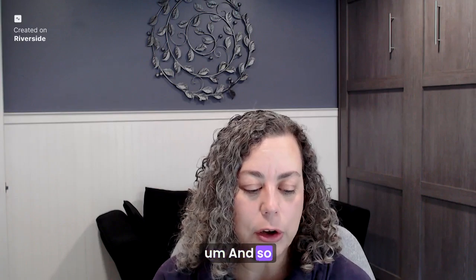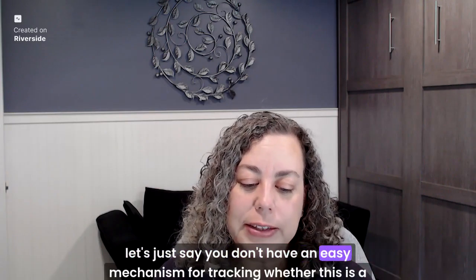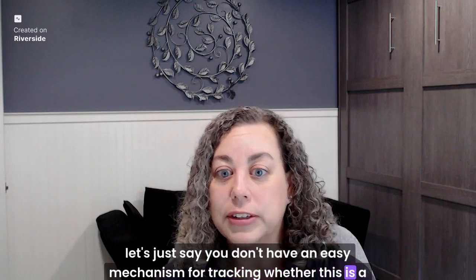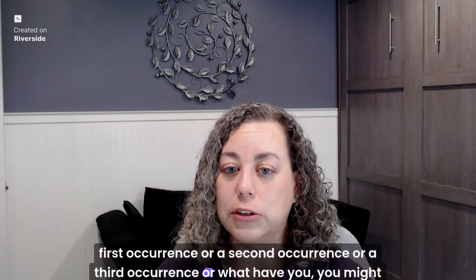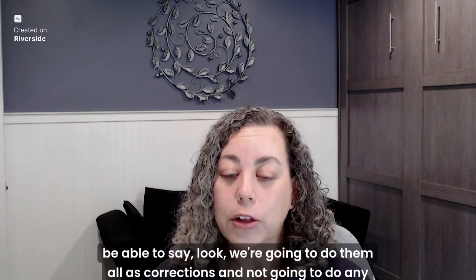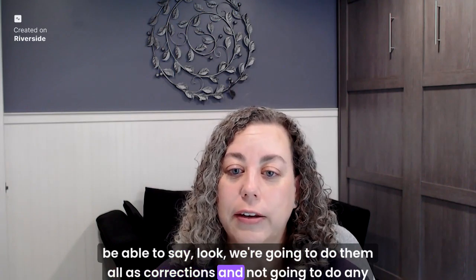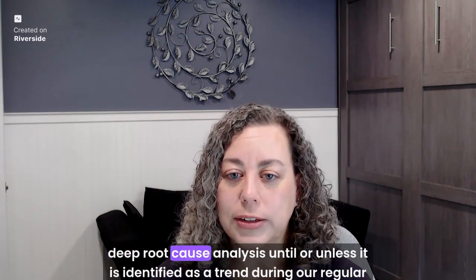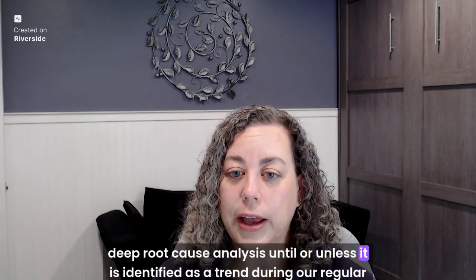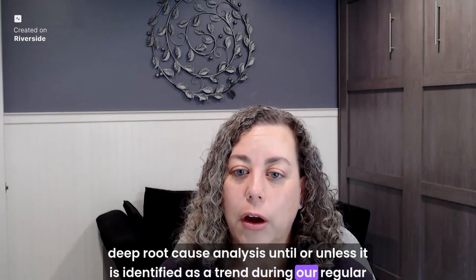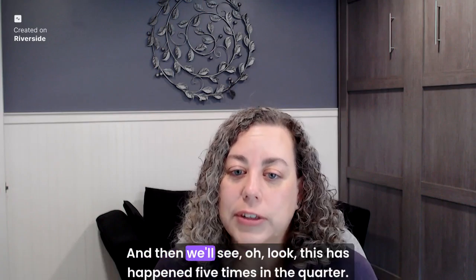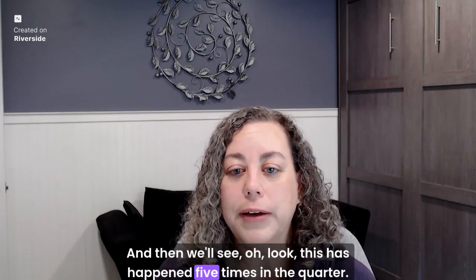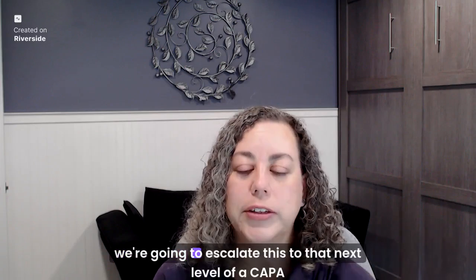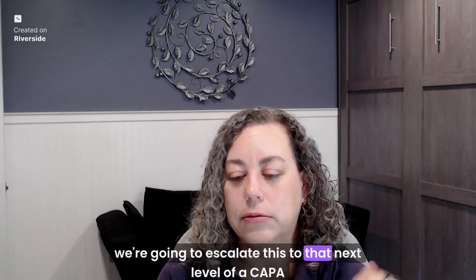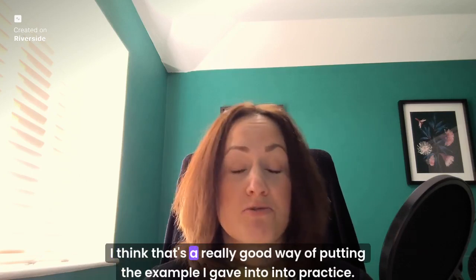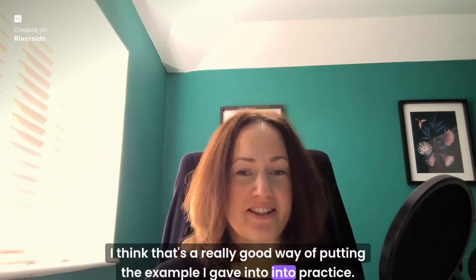And so let's just say you don't have an easy mechanism for tracking whether this is a first occurrence or a second occurrence or a third occurrence or what have you. You might be able to say, look, we're going to do them all as corrections, and we're not going to do any deep root cause analysis until or unless it is identified as a trend during our regular trending activities. And then we'll see, oh, look, this has happened 5 times in the quarter. We're going to escalate this to that next level of a CAPA.